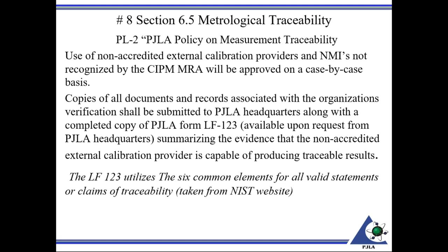Now we also want to interject some things in PL2 here because it correlates with the requirements in 17025 section 6.5. You could be providing traceable measurements and not be accredited. We take this into account, and we have a protocol to follow in this instance that's in harmony with the requirements of 17025. We have a form that needs to be filled out, and particular objective evidence would need to be provided. So if you happen to be using a provider who is not accredited, who's claiming traceability, and you want to continue to use that provider, you can still hopefully utilize them. You just have to show objective evidence of their traceable measurements.